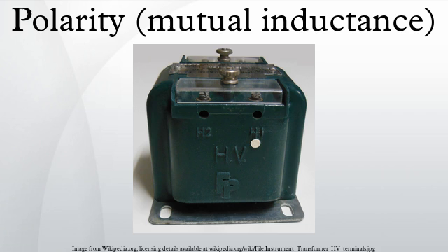The polarity of a device with mutual inductance designates the relative instantaneous current directions of such devices' winding leads. A dot marking convention, or alphanumeric marking convention, or both, can be used to denote the same relative instantaneous polarity of two mutually inductive components such as between transformer windings. These markings may be found on transformer cases beside terminals, winding leads, nameplates, schematic and wiring diagrams.